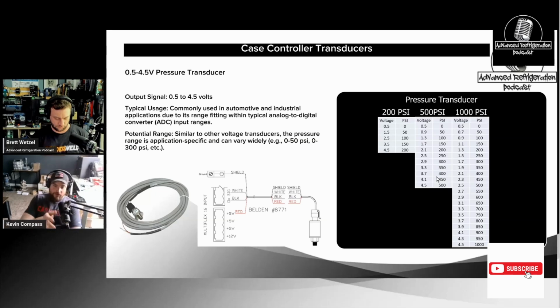Now, looking at this multi-flex board, you'll notice the black wire is hooked to 0 volts — 0 volts is ground. That's different from the shield ground, which is the physical ground of the rack or cabinet. That black wire goes to 0 volts. Danfoss calls it signal and ground, Micro Thermo calls it signal and ground, Copeland calls it signal and 0 volts. So that's where you want to check it.